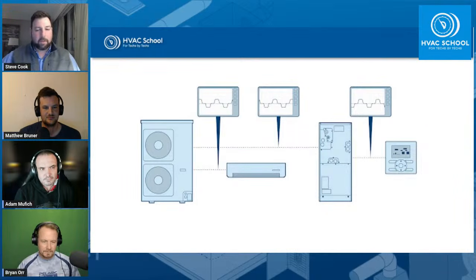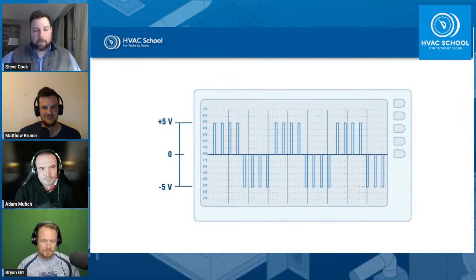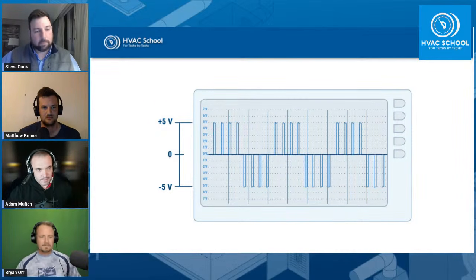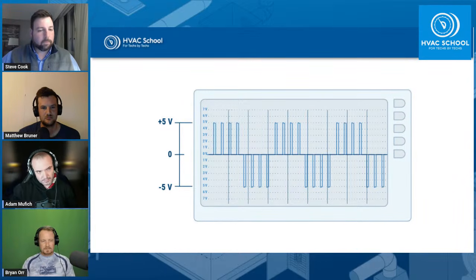So the pulse is, so I can't recall. Let me rephrase that. Let's say you disconnect the wire outside and you're reading the voltage. Are you going to see voltage being sent from the indoor unit to the outdoor unit, and vice versa? Like, let's say you disconnect the wire on the inside. Oh, I see what you're saying.